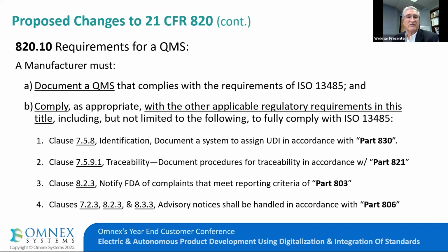A couple of those clauses, for example, clause 7.5.8, identification: the UDI in accordance with part 830 describes what that unique device identification has to meet. 7.5.9.1 for traceability: you must have the traceability in accordance with 13485 and part 821, which is the medical device tracking requirement.